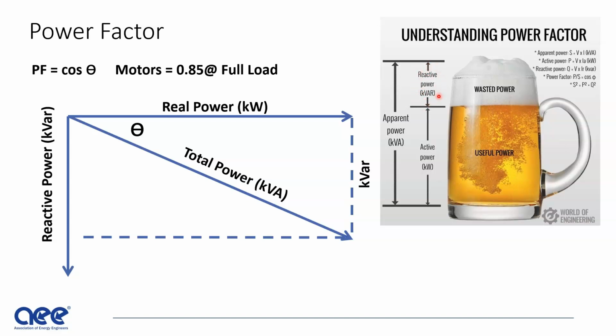Without reactive power, you don't magnetize the steel in the motor, you don't magnetize the steel in transformers, and guess what? We're back in the Stone Age because we have no electricity. Reactive power is key to magnetizing steel in our motors and our transformers. It's not wasted, it's purposed very intentionally to create the magnetic field that is needed for transformers and motors to work.